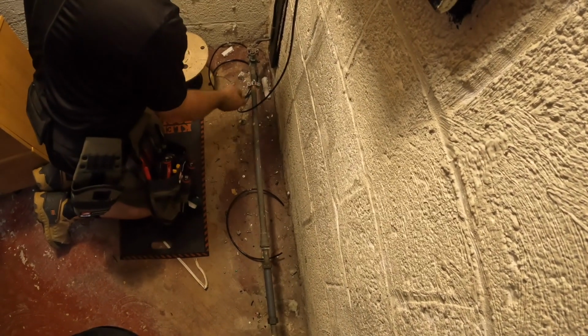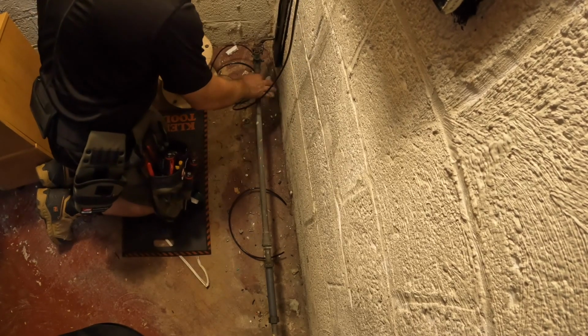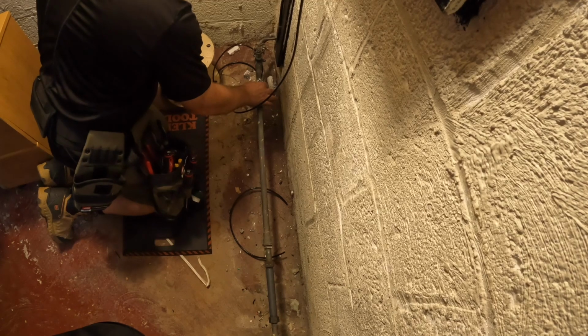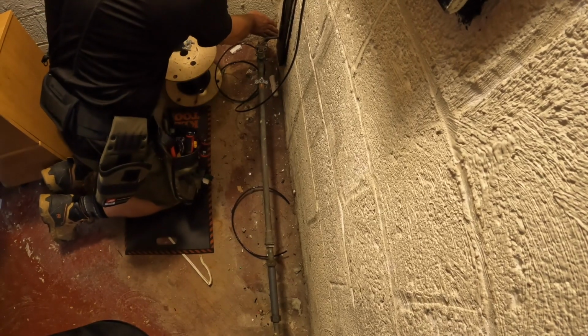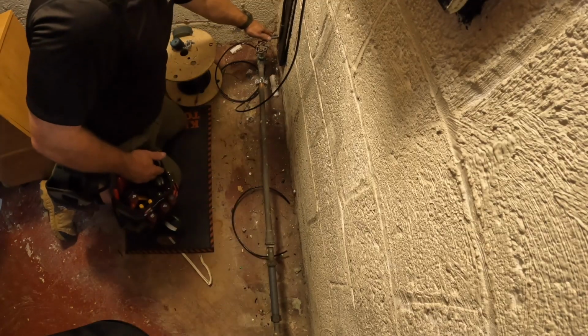We bond this piece of pipe right here with our grounding electrode conductor to our grounding electrode via this clamp, and now this copper water pipe becomes our electrode because it's connected inside the earth. And let's just see if this water heater is already jumped out. It is. I hope you could see that right there. So the cold water comes in one of these sides. I'm not sure which side, but it comes in on one of these sides and it goes out hot. So what we need to do is put this jumper in so that all of the copper water piping in the system is bonded to the grounding conductor here at the main disconnect.